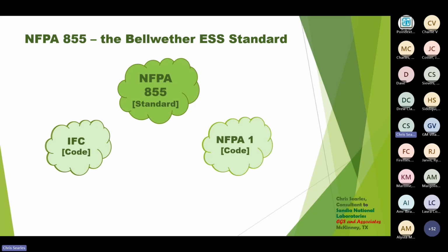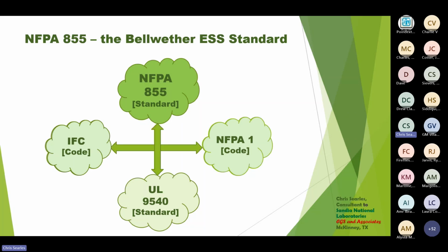They're dependent on the two codes we've been talking about, the IFC and NFPA 1. Now we do need to add UL 9540 into the equation, because it's referenced in all of the standards and codes we're talking about, pointing to 9540 as a necessary listing required in order for your energy storage system to be qualified and compliant with 855.